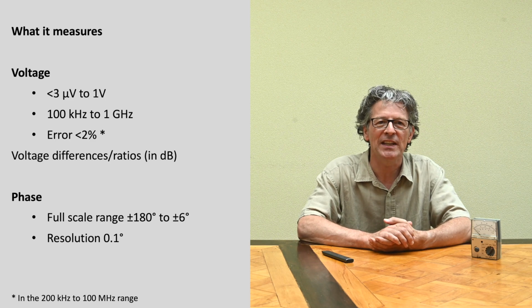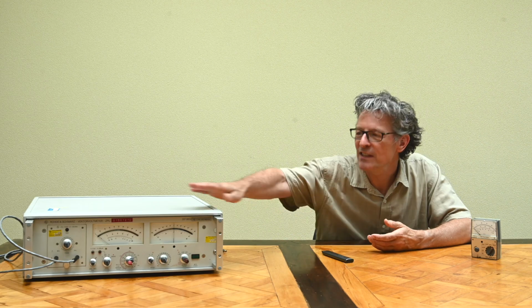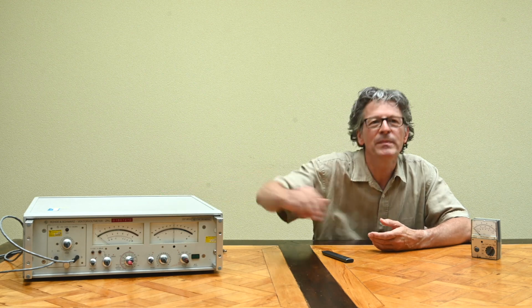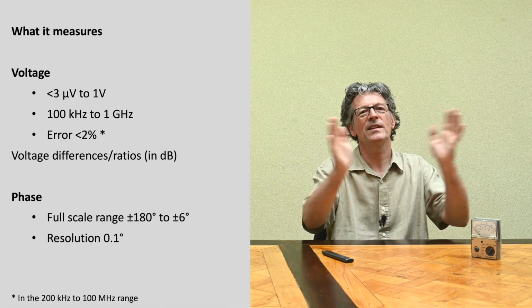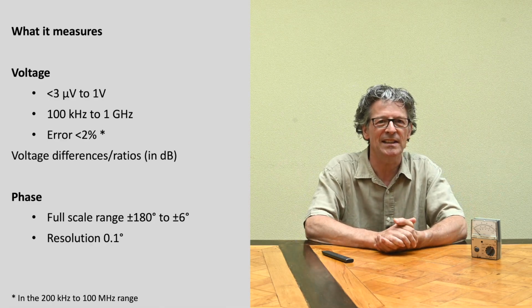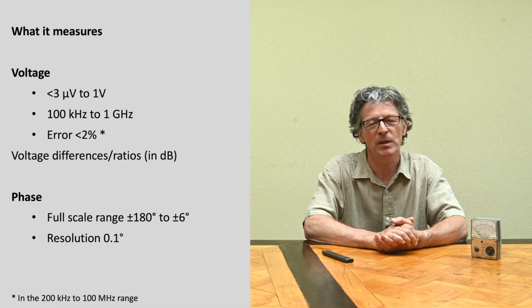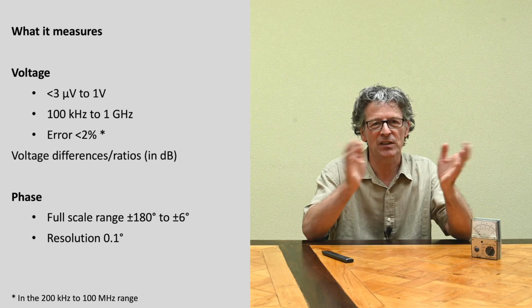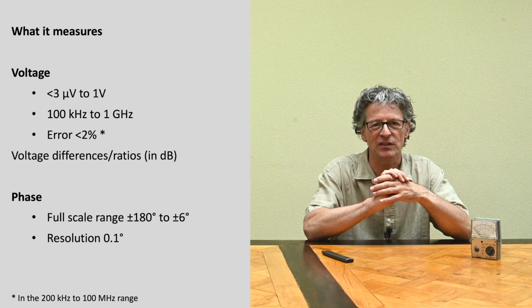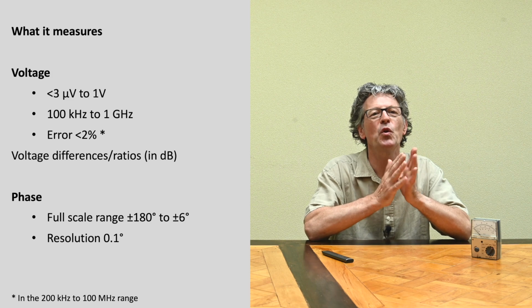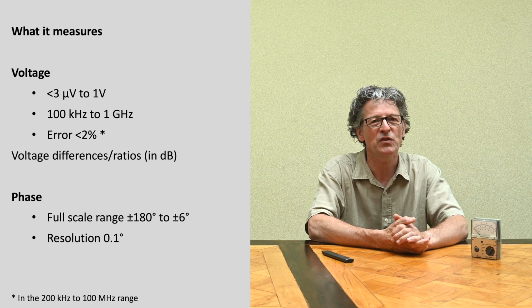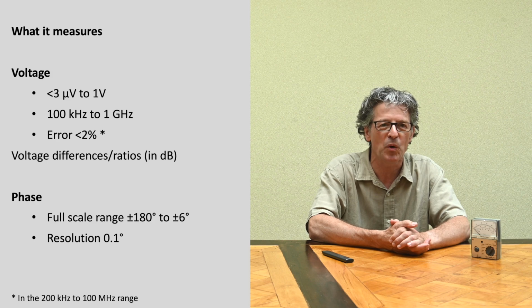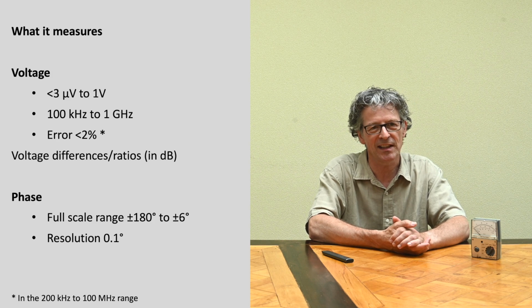And you can do phase testing. You have a phase tester, that's the other analog meter right over here. It can show phase from minus 180 to plus 180 degrees, but you can also let the meter just show you minus 6 up to plus 6 degrees for small phase differences. And according to the specifications, we could measure phase all the way to a resolution of 0.1 degrees. So that's already quite impressive, I think, in terms of specs.